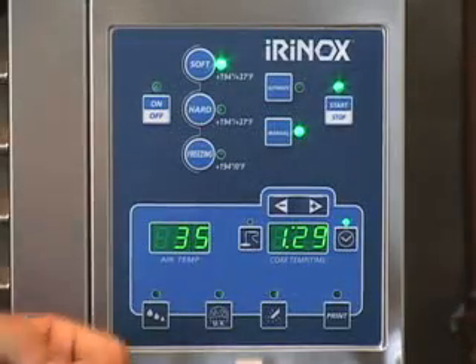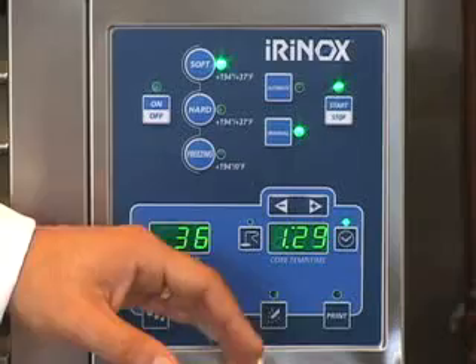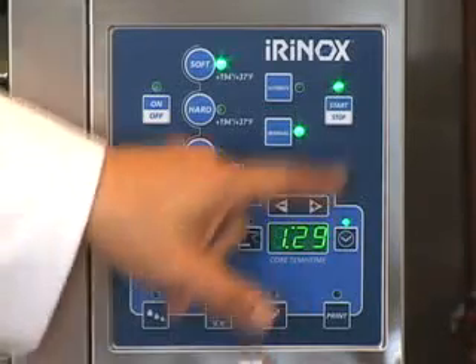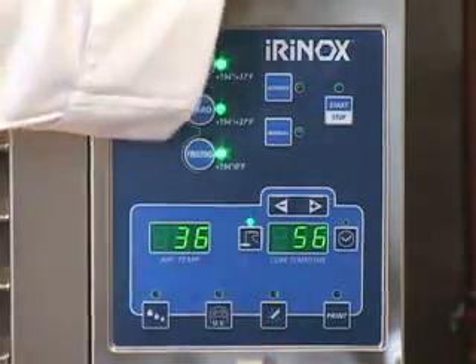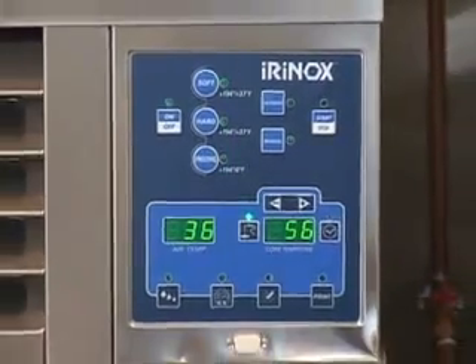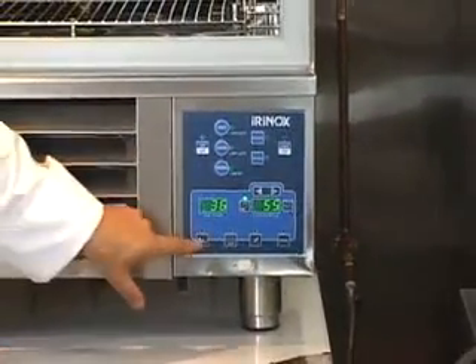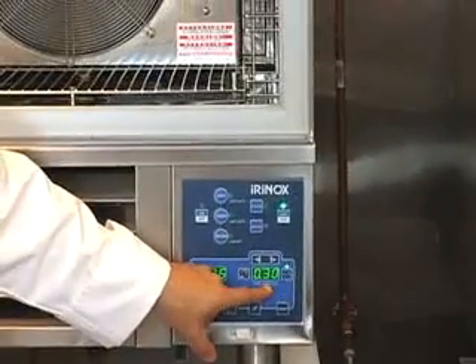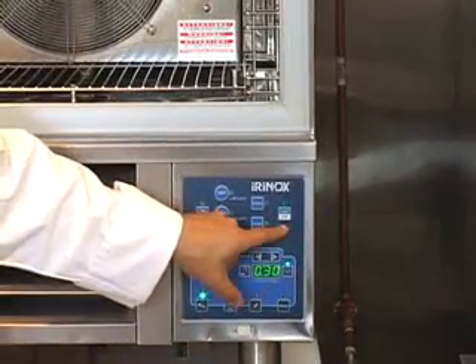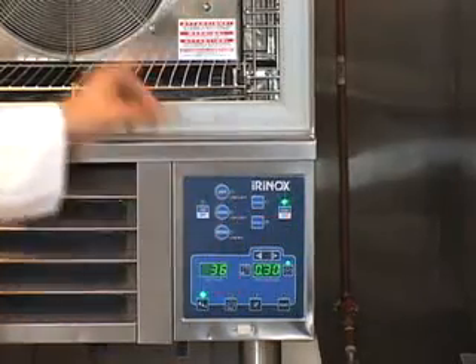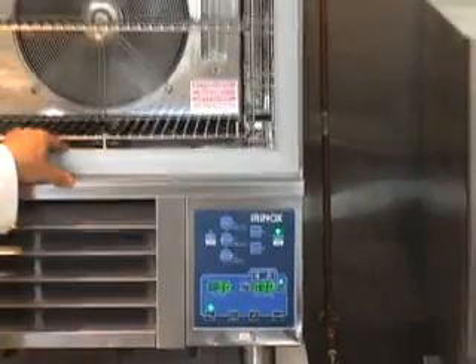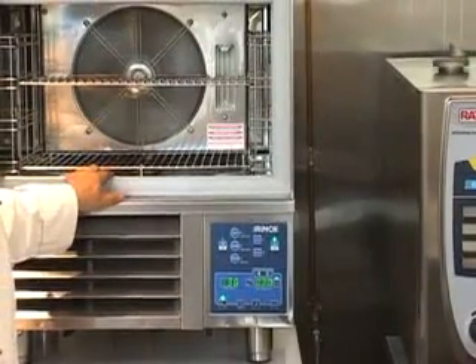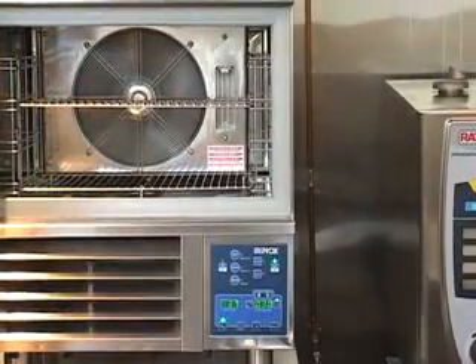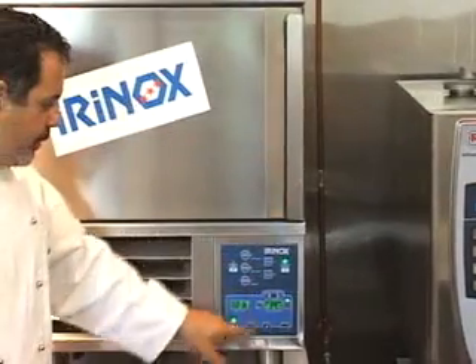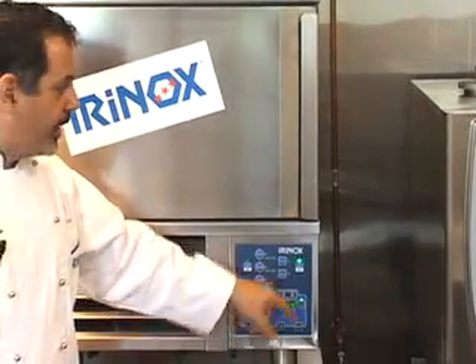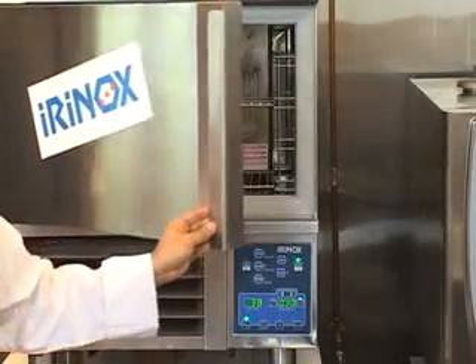I'm now going to demonstrate the defrost cycle. When I have finished chilling or freezing the products that I need to do, I hit the stop button on the unit. I now can open the door and leave the door open. The door must be open for the defrost cycle to operate. I hit the defrost button. It's preset again at the factory for a 30-minute defrost. You'll notice the start button is flashing. I hit the start button and the fan will come on. The unit will run for 30 minutes and defrost the unit. If I close the door, I'll get an error message telling me that the door is closed and I need to keep the door open until the defrost cycle has been completed.